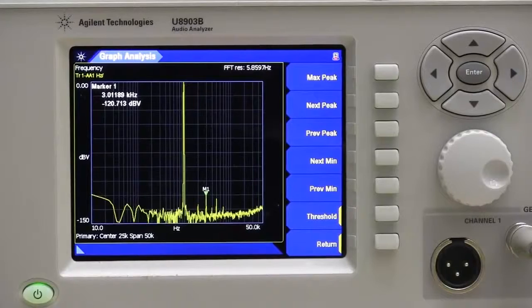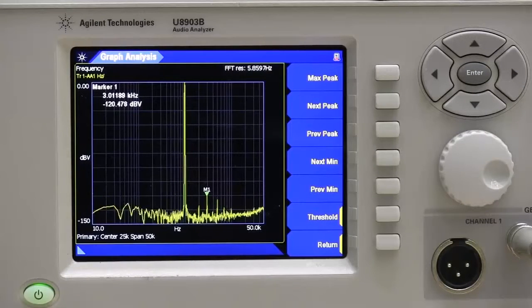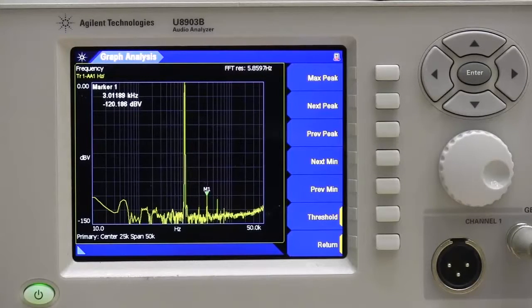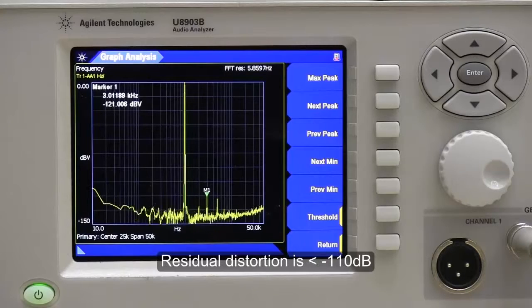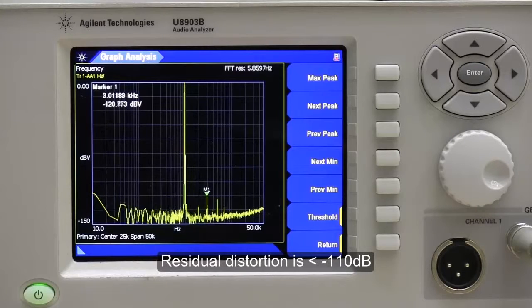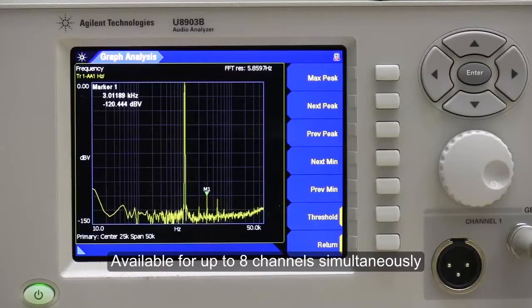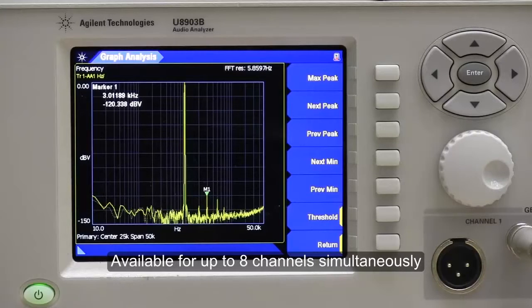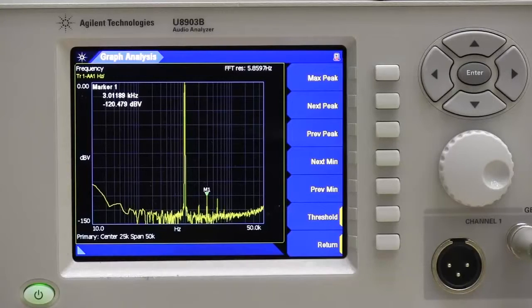The U8903B comes with extremely low residual distortion and noise. The residual distortion is less than negative 110 dB, enabling the measurement of the most demanding devices. This performance is available for up to 8 channels simultaneously. As you can see here, this is an FFT plot showing the residual distortion.